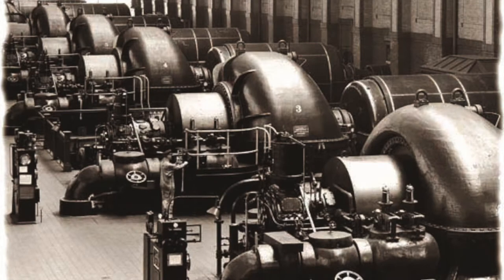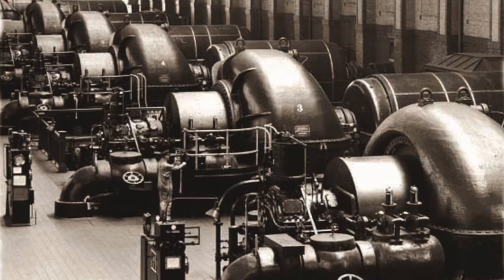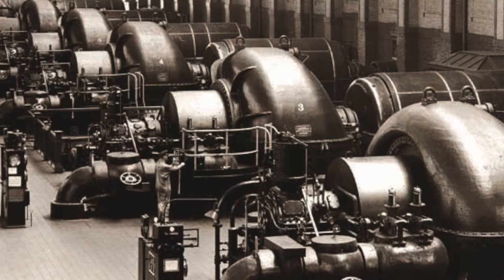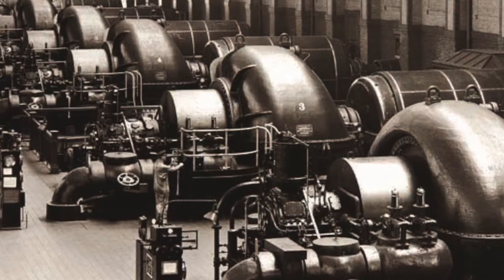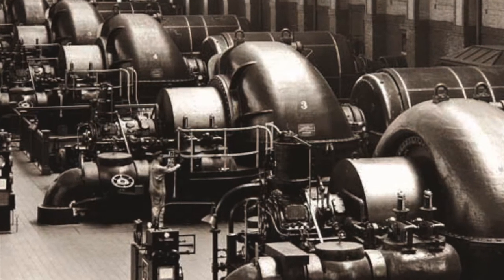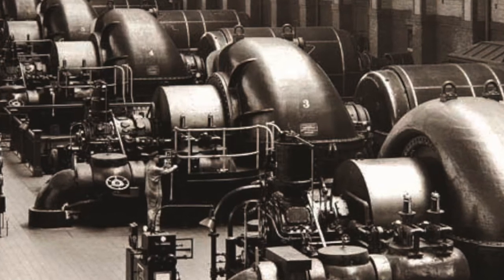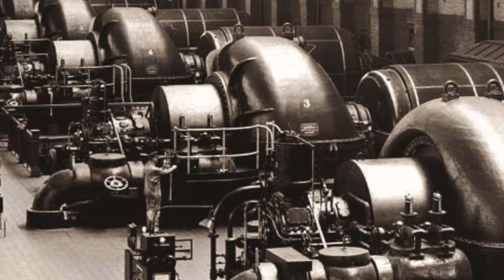Traditional steam turbines, especially those from the 1950s like the one investigated in this project, are meant to modulate output power near 100% capacity. However, when power output from renewables is highest, the turbine must ramp down to operating around 20% capacity.